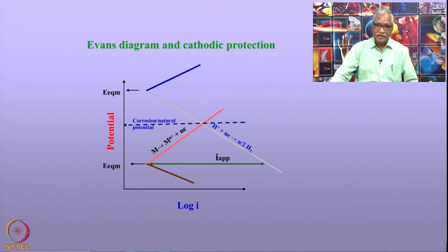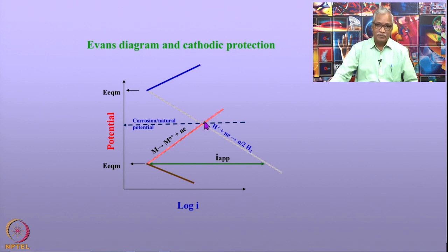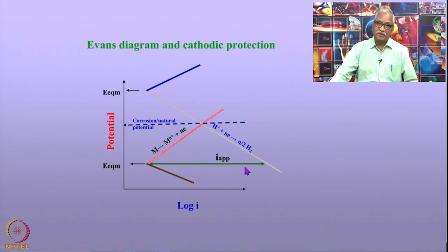In cathodic protection criteria, we bring down this potential from the natural potential to as low as possible. Ideally, you should bring it down to the equilibrium potential as shown in the diagram. Below the equilibrium potential, the metal is completely immune to corrosion. Any potential at which you hold the metal has a corresponding corrosion current. To completely prevent corrosion, you need to bring the potential to the equilibrium potential, but that also means we need to supply a large amount of current.